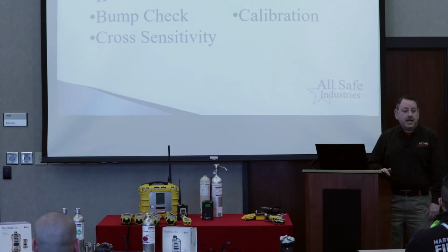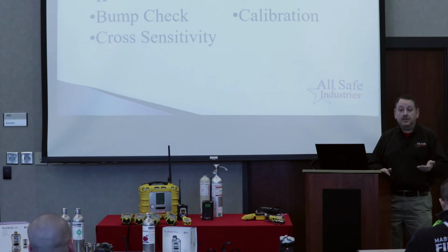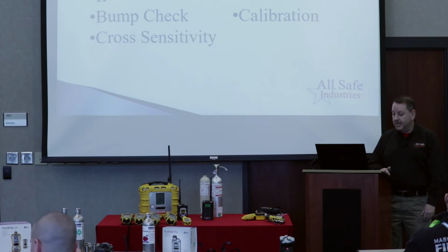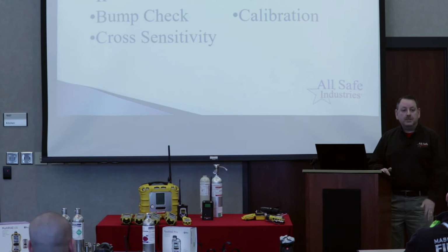I had a customer that had ammonia sensors, and they were getting some readings in a part of the plant. They knew there was no ammonia in this particular area, and so they called me and they started investigating. Well, it turns out the ammonia sensor is cross-sensitive to acetylene, and sure enough, they had a torch set up in the space, and they had a leak on the acetylene line. And so that acetylene leak had a reaction to the ammonia sensor, and so the gas meter did its job. It alerted them that there was some sort of gas present and some sort of reaction was happening so that there was a reading on the sensor. Okay? So a lot of terminology. You'll get more comfortable with it as we track through this.